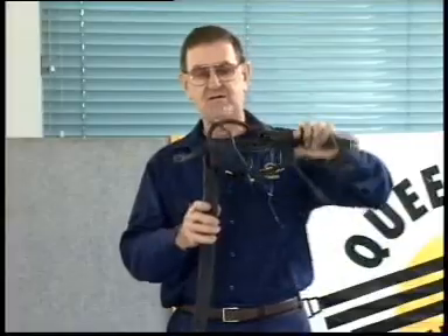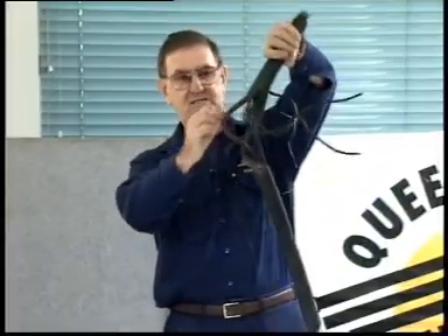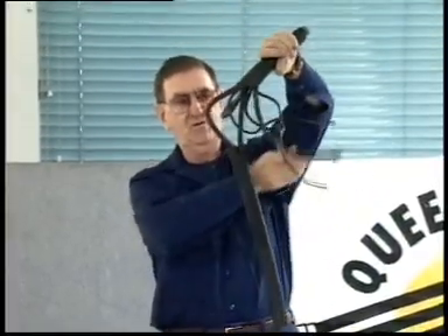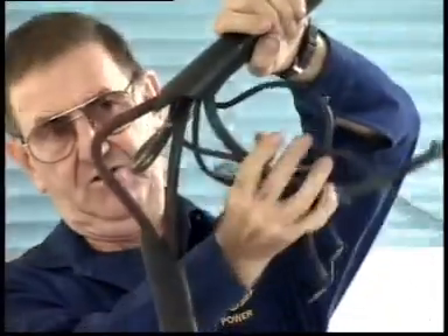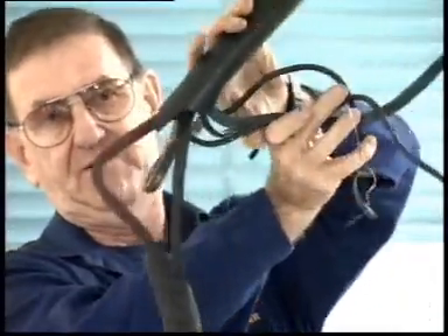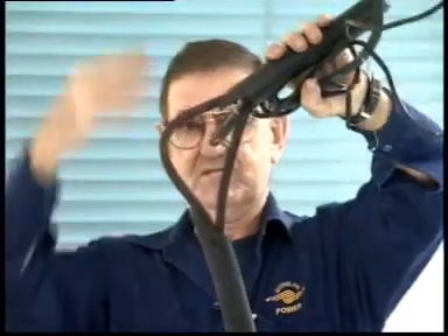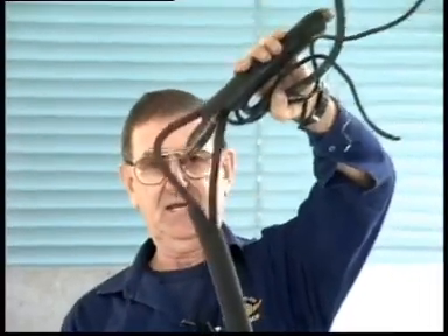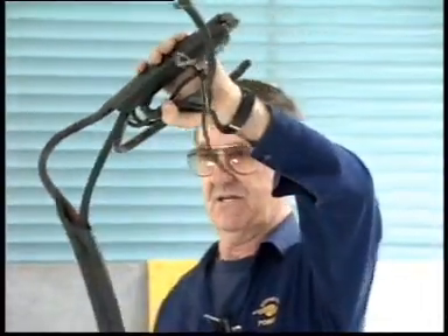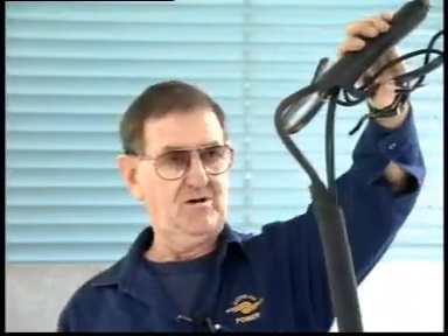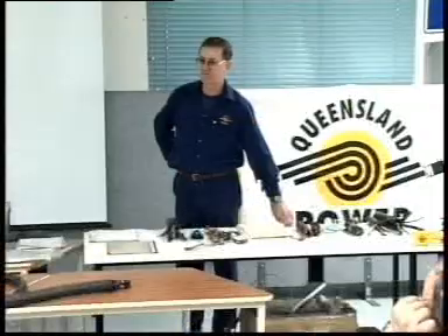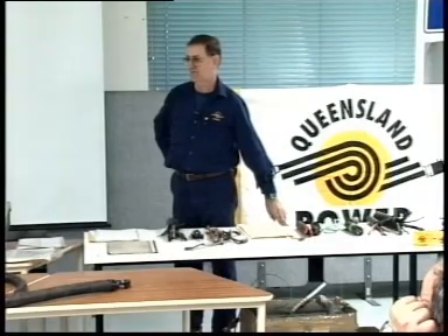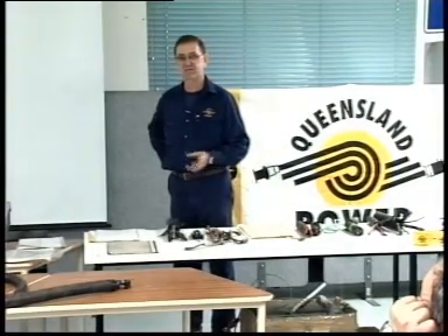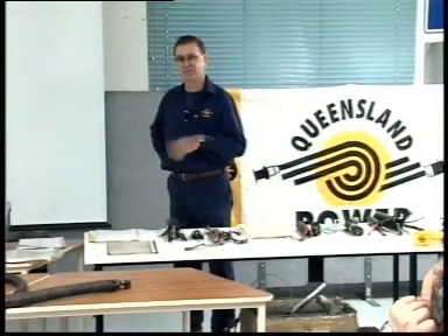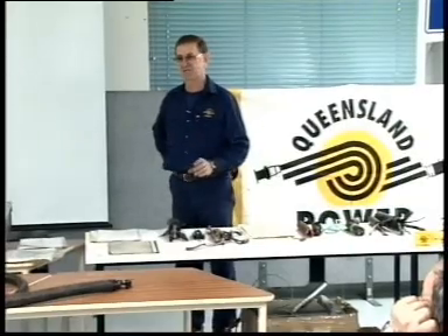It's not. There's one here that we've got. It's got the white phase and the blue phase completely pulled in half, and all of the 3 earth wires pulled in half. We've got the red phase which has started to pull out, and it's obviously broken down here, and hanging right in the middle of it, still intact, is that little piddly pilot wire. We have to make sure that the cable is completely symmetrical at all times, which means that there's no out of balance between the phases inside and the earth system that's inside.